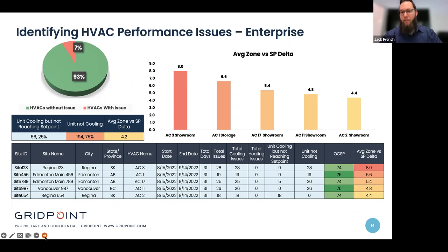So the bar chart is sorted by the units that were the farthest from their set point. So the highest average zone versus set point delta, these are just the top five most severe for this reporting period. So you can see that top one at Regina AC3 was an average of 8 degrees above its set point. That's really significant. So, first of all, we want to make sure that the unit is properly maintained. So potentially, roll a truck, especially if this is consistent, which it really is. And then second, make sure that the occupied cooling set point is at or above best practice. And in this case, it already is. So this was a significant issue that the customer ended up having to roll a truck for to get resolved. And they made a data-driven decision to lead them to that conclusion.